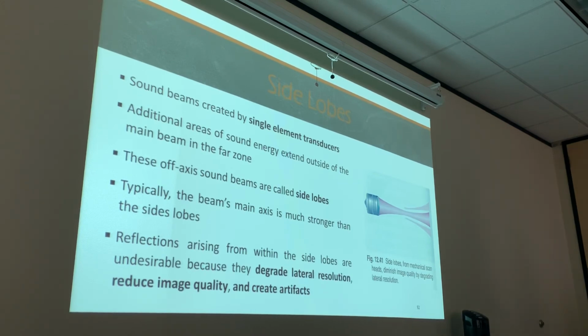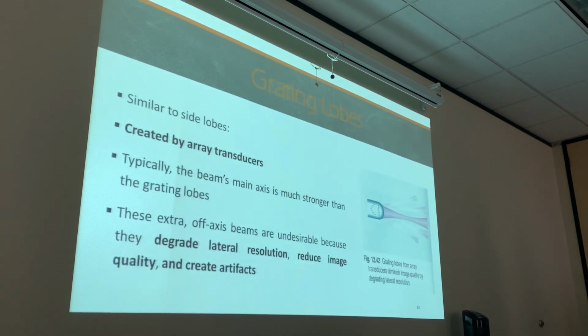Reflections, meaning after the sound beam has traveled into the body, even the side lobes have reflections as well. Those weak reflections coming from the side lobes are undesirable because they degrade lateral resolution, reduce image quality, of course, and create artifacts. Again, they're creating noise on our image. We don't like side lobes at all. Side lobes are associated with single element transducers. Just with the single? Just for single.